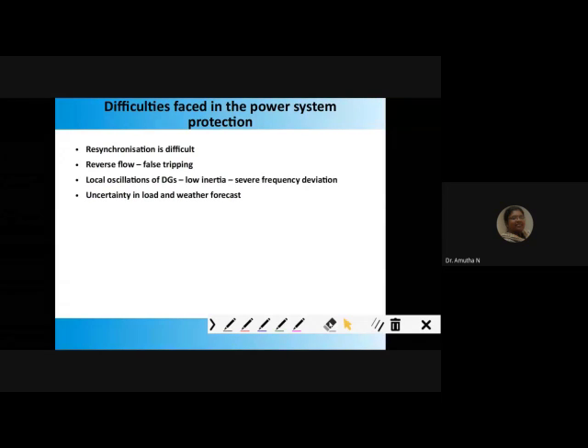Because of this, synchronization with the utility grid may become a problem. Once during a fault the utility grid is separated from the microgrid, it goes into islanding mode. At that time some distributed generators may be supplying loads while others will be off, so resynchronizing all these distributed generators becomes difficult.